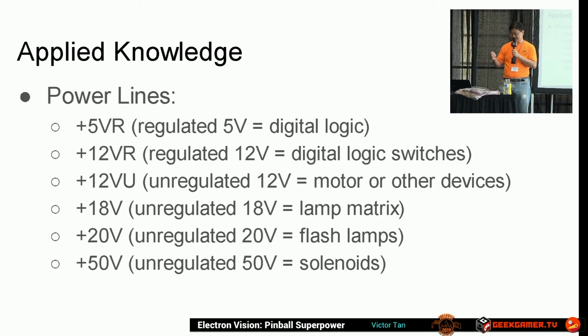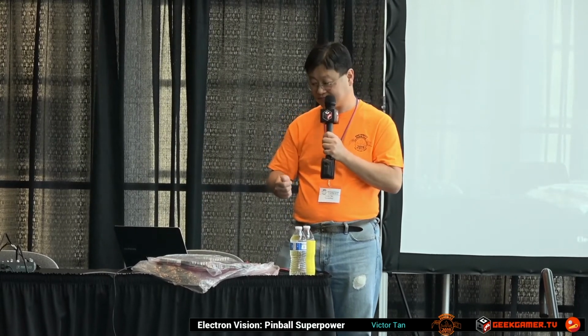And if it all roots back to the optos, you need to check your 12-volt regulated. The CPU uses the 12-volt regulated for comparison of switches. If the switch is closed, current flows, and the voltage is 0 when current flows. If the switch is open, current doesn't flow. There is a potential difference across the two wires. The voltage is 12 volts. The CPU senses that and says the switch is open. That's all the logic is. It's digital logic. It's either 0 or it's 1. It's either open or it's closed.